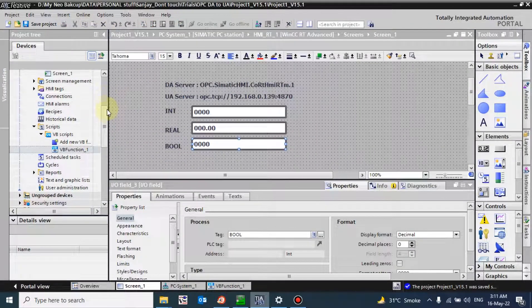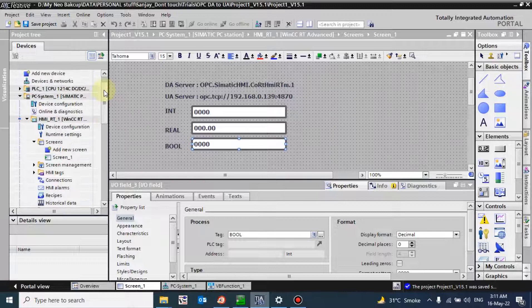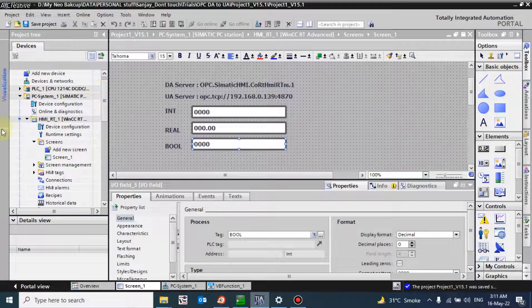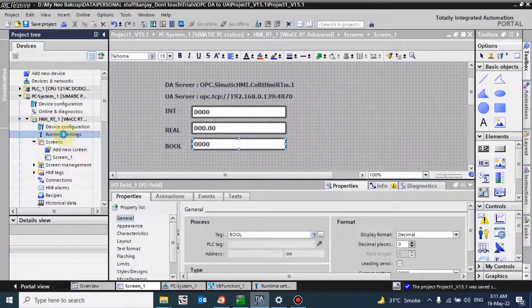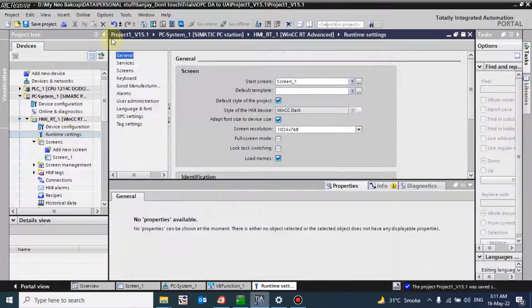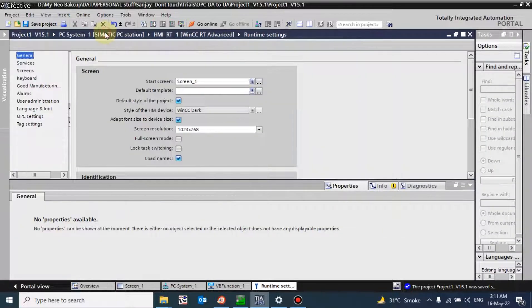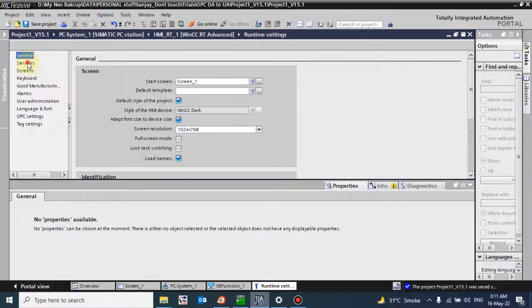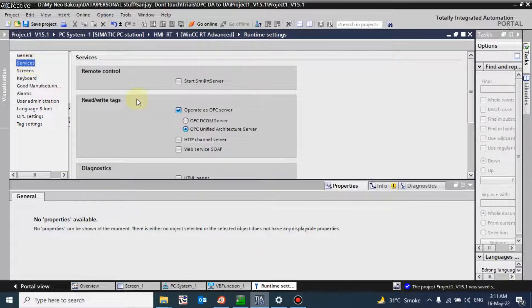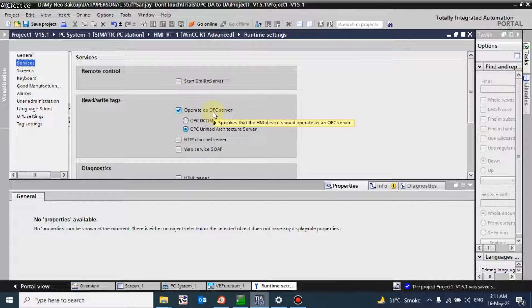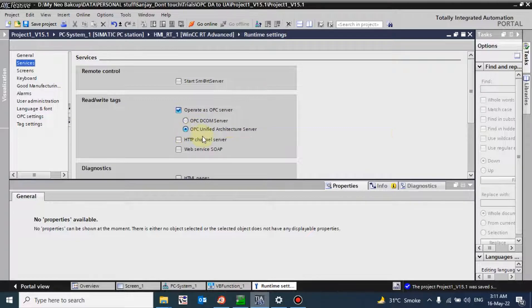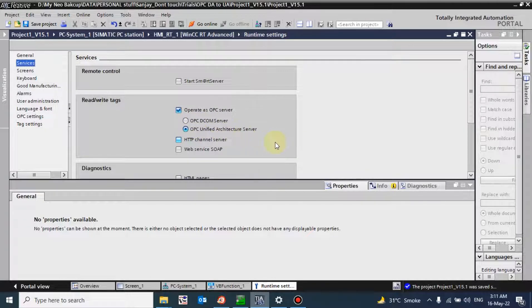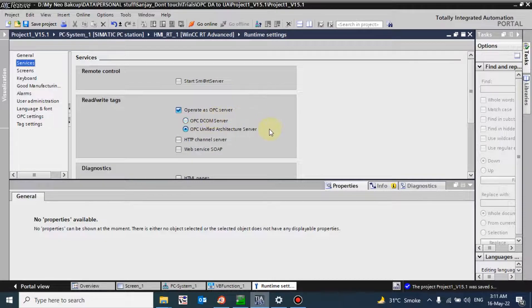Now how to activate the OPC UA server in our Siemens WinCC SCADA. For that you have to go to the runtime settings, go to the services, and there you have an option to operate as the OPC server. There are two options: OPC DCOM server, which means data access server, and there is OPC unified architecture server. These two options are available.